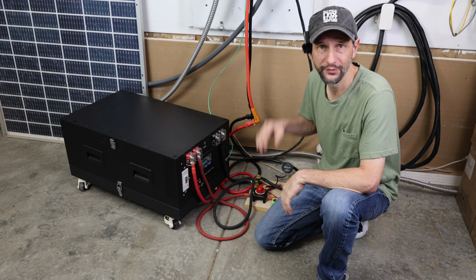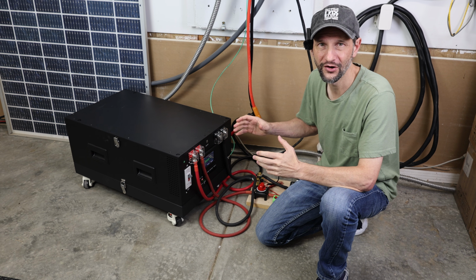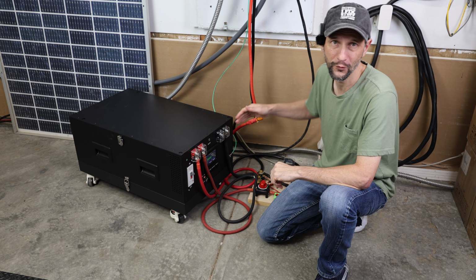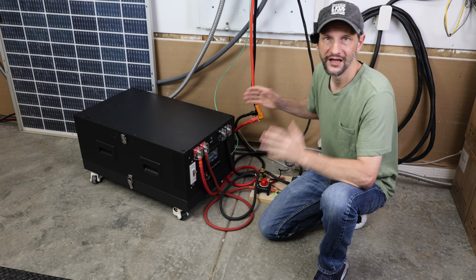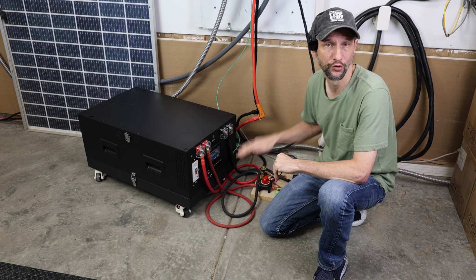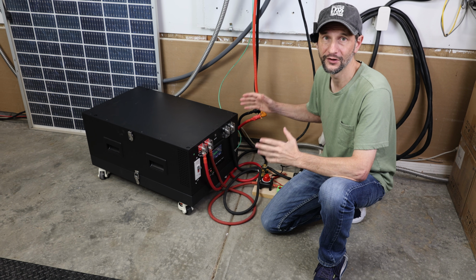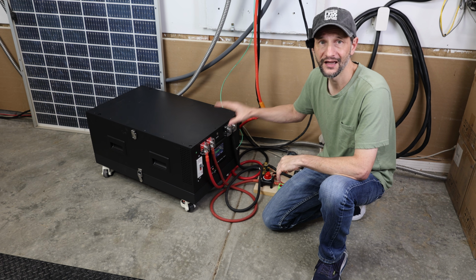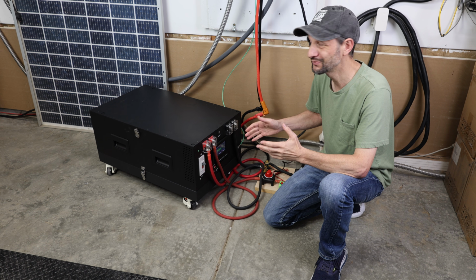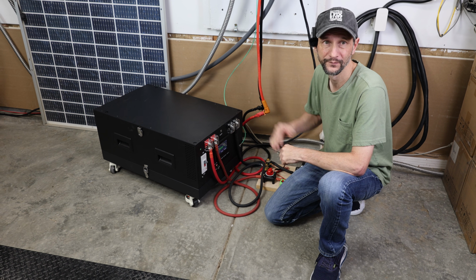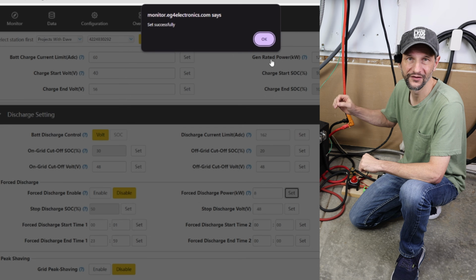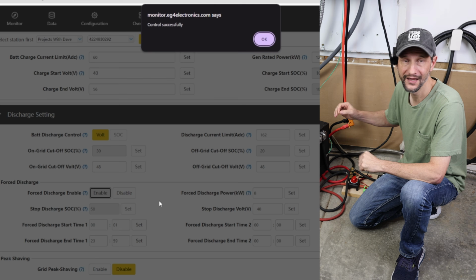Now, just for fun, let's push the limits a little bit. If I want to charge my car, it takes about 8 kilowatts, the maximum output of this inverter. If I was using a server rack battery, I would need multiple batteries to achieve that level of discharge current. But this pack has a 200 amp BMS, so it should be able to support up to 10 kilowatts. To simulate the car charging, I'll set the forced discharge to 8 kilowatts, and let's see what happens.